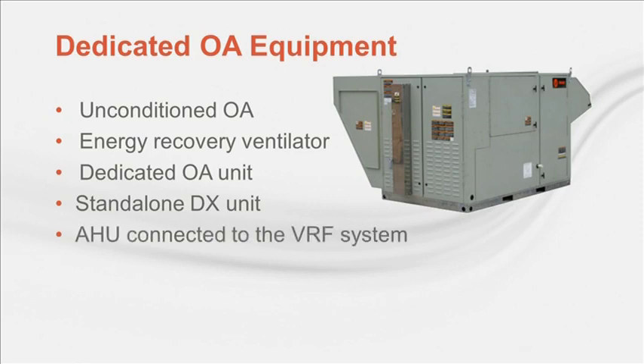But other systems use an air handler where the DX coil is connected to a VRF system. This can allow for simultaneous cooling and heat recovery during colder months, if the system also serves interior zones that still require cooling, while the outdoor air must be heated. However, remember that in the summer, both the outdoor air unit and indoor units will be in cooling, so you're limited on the circuit size. And at least today, there's often a low limit on how cold of air can be heated, possibly requiring the addition of preheat.